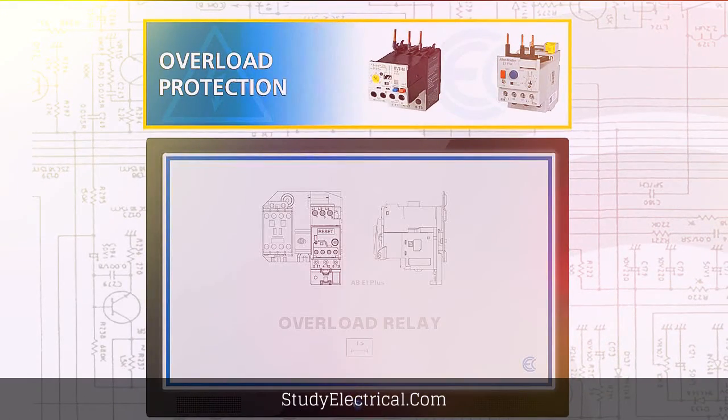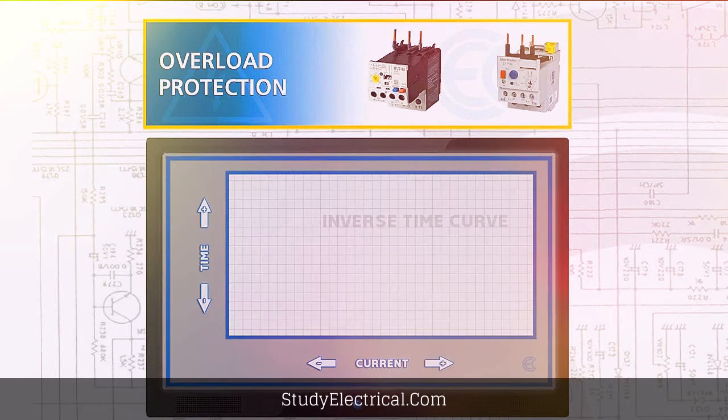Overload protection is protection against a running overcurrent that would cause overheating. Overload protection typically operates on an inverse time curve where the tripping time becomes less as the current increases. This means an overload relay isn't going to trip on momentary or short-term overcurrent events that are normal for the piece of equipment it's protecting.